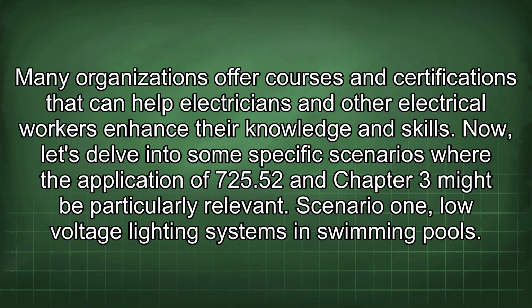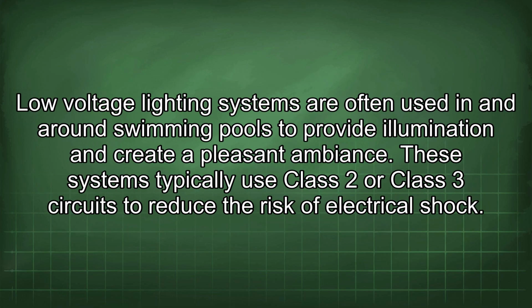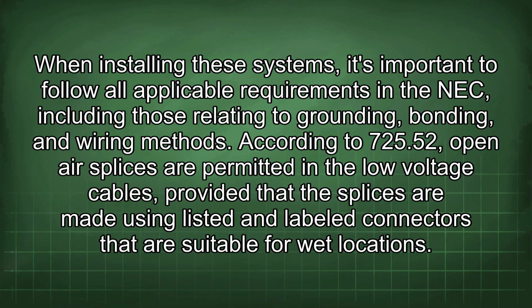Scenario 1: Low voltage lighting systems in swimming pools. Low voltage lighting systems are often used in and around swimming pools to provide illumination and create a pleasant ambience. These systems typically use Class 2 or Class 3 circuits to reduce the risk of electrical shock. When installing these systems, it's important to follow all applicable requirements in the NEC, including those relating to grounding, bonding, and wiring methods. According to 725.52, open-air splices are permitted in the low-voltage cables, provided that the splices are made using listed and labeled connectors that are suitable for wet locations.